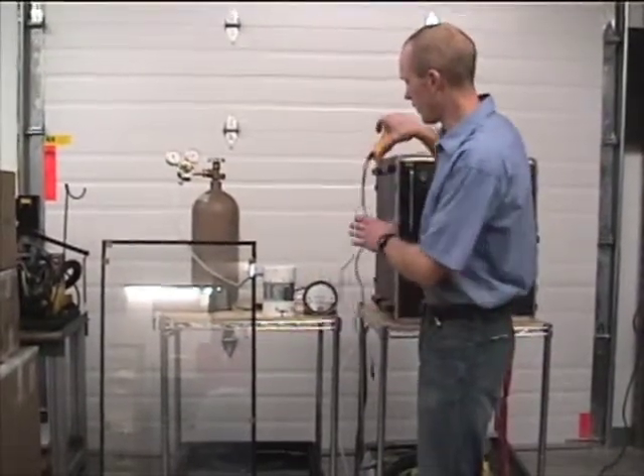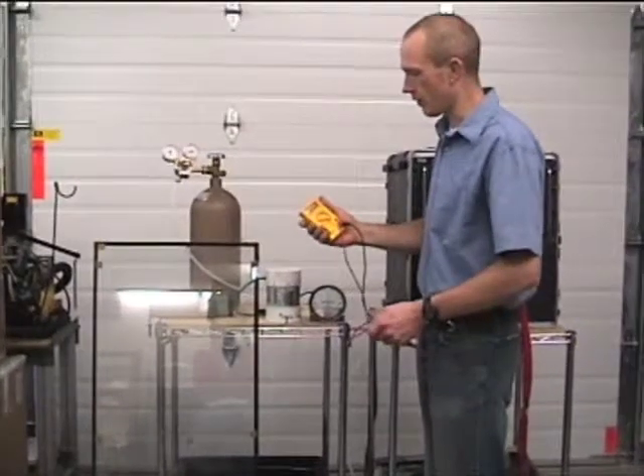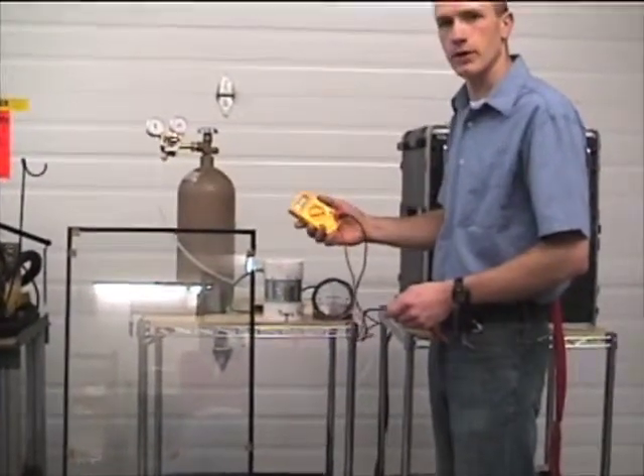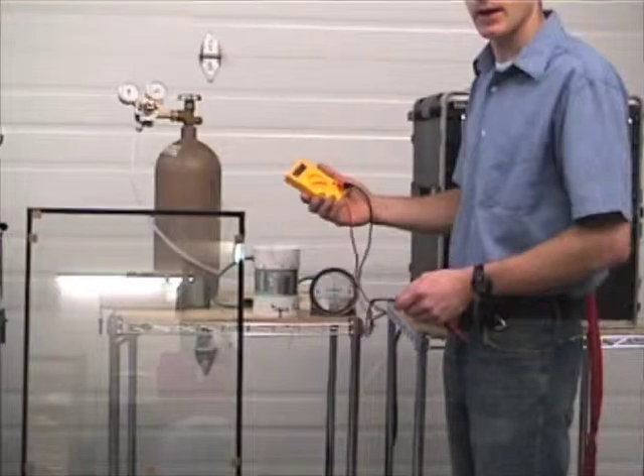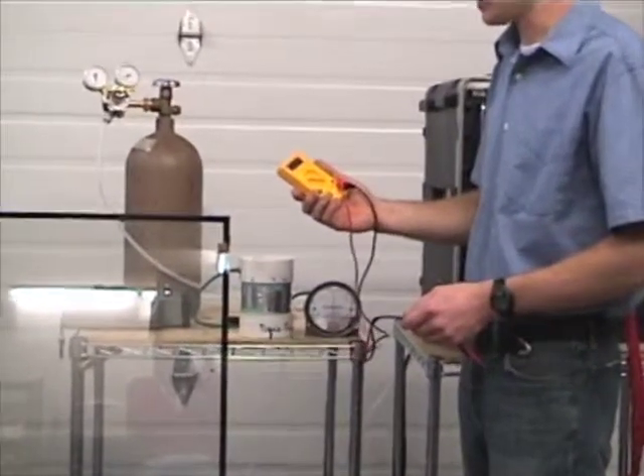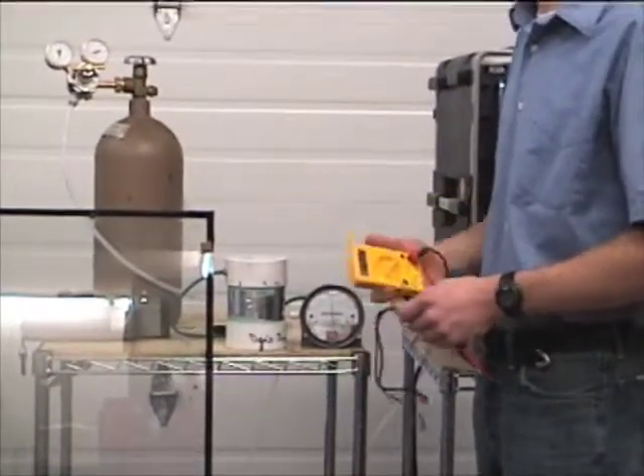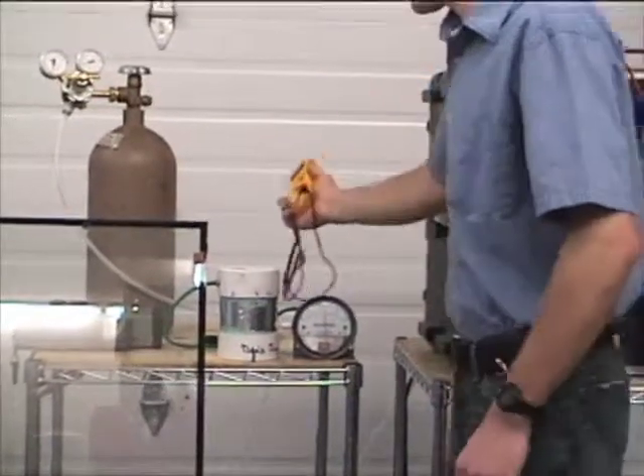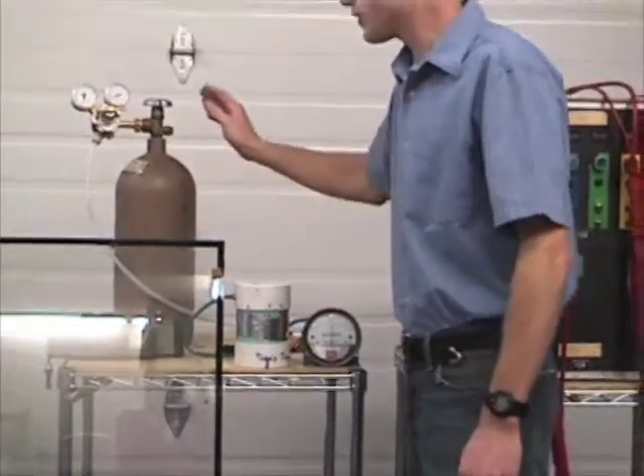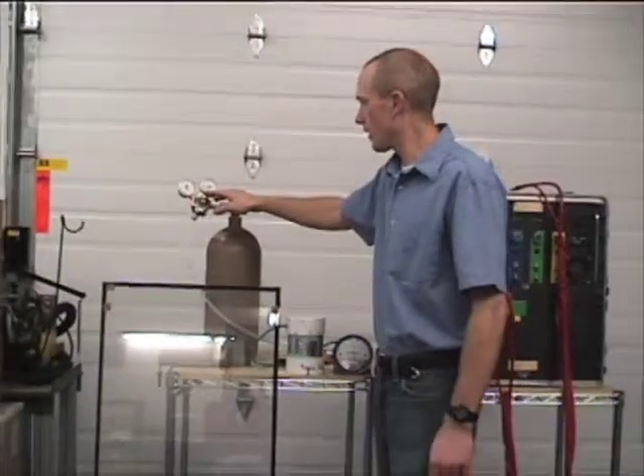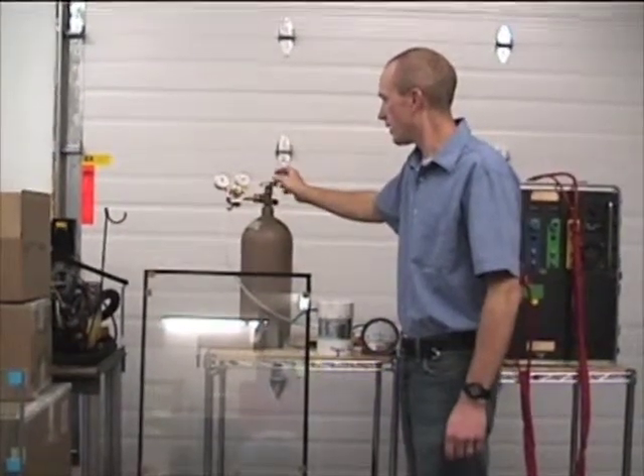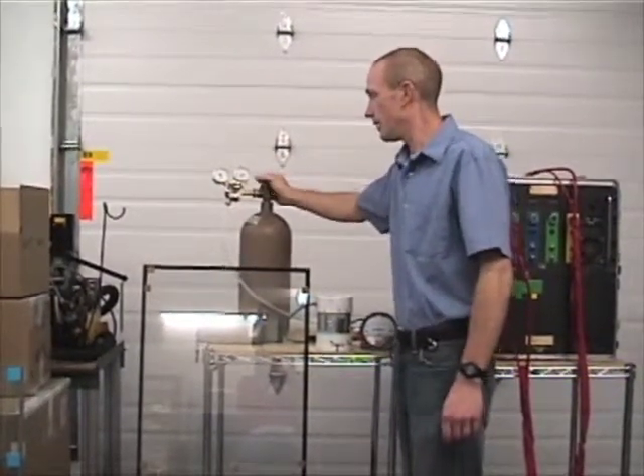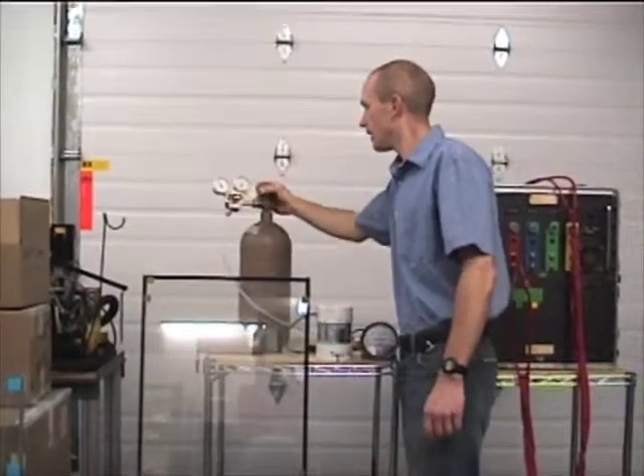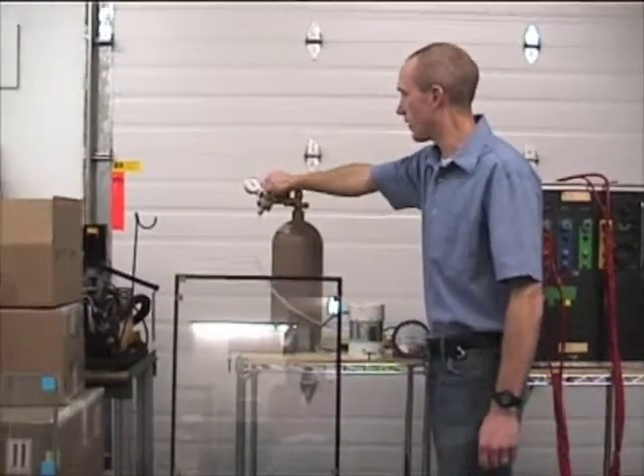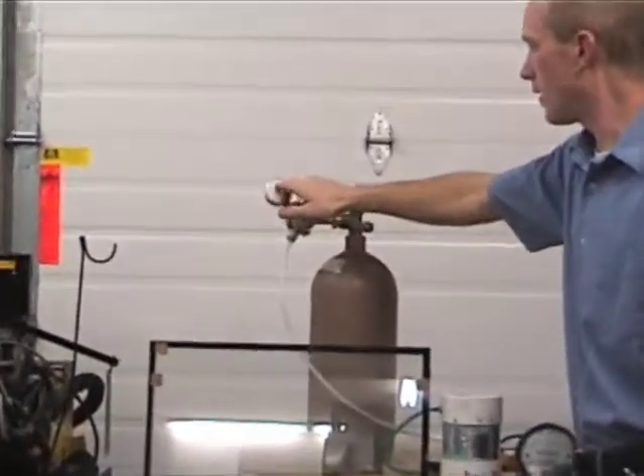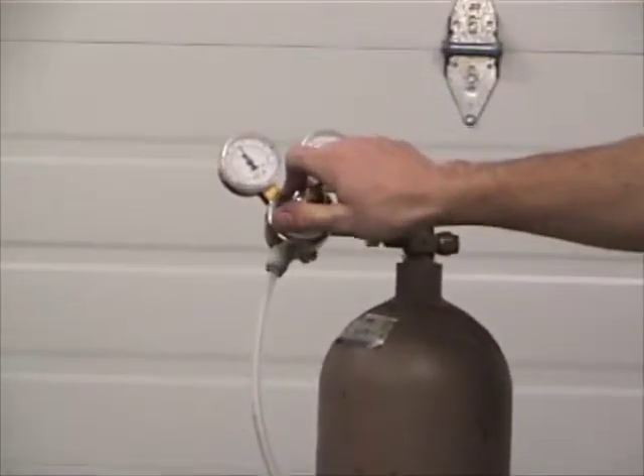Another thing that's shipped with your machine is just a standard voltmeter, and for the calibration process we'll be using this in the DC volt setting to do the calibration of the machine. The next thing that's shipped with your machine is an argon regulator, and this you'll want to set at about 80-85 psi. And to do that, you just turn this adjusting knob and read the gauge.